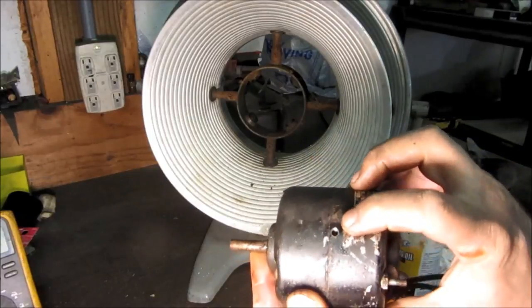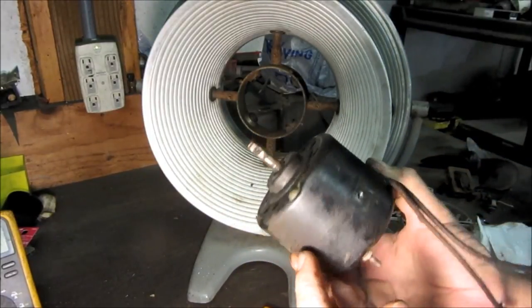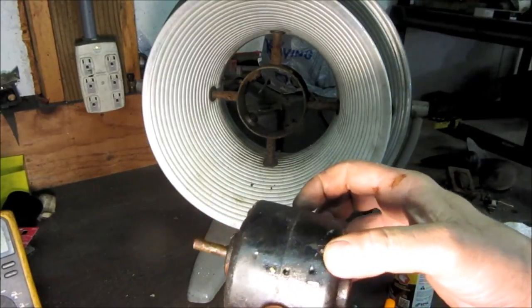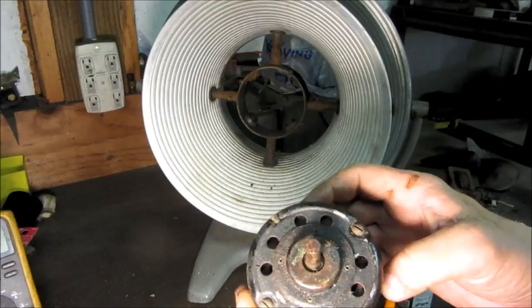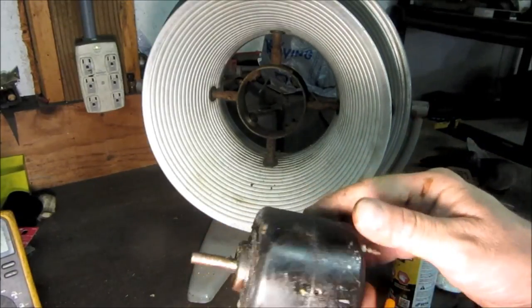After getting the motor out, I found out they've drilled and tapped these four holes in the side of it, and those go through the shell and into the stator laminations. So if I take this apart and I can't get that to line back up exactly, it's gonna be a problem.